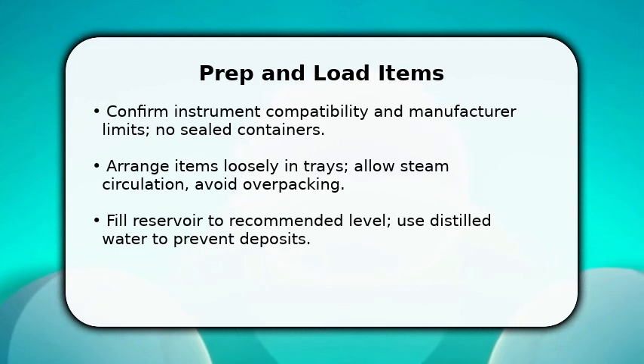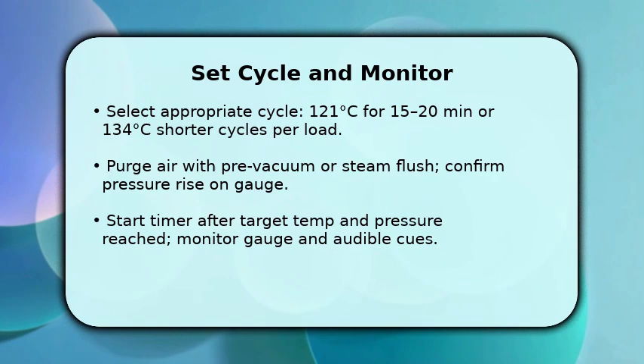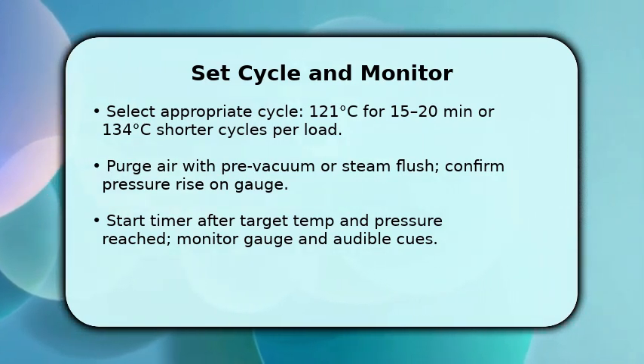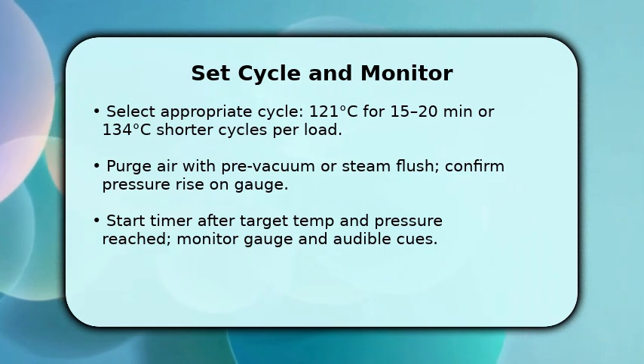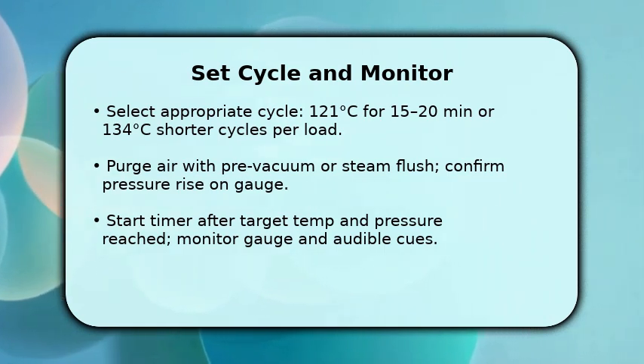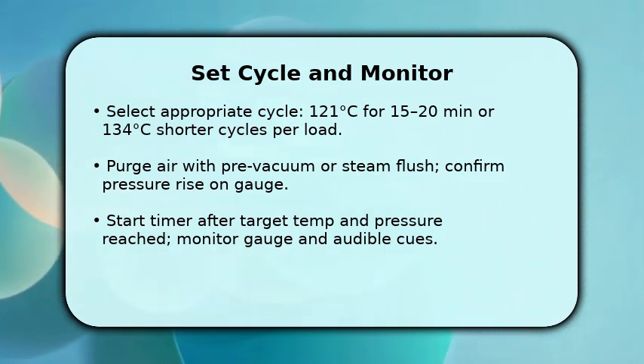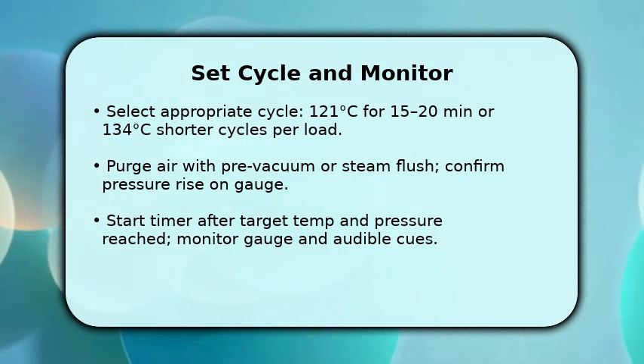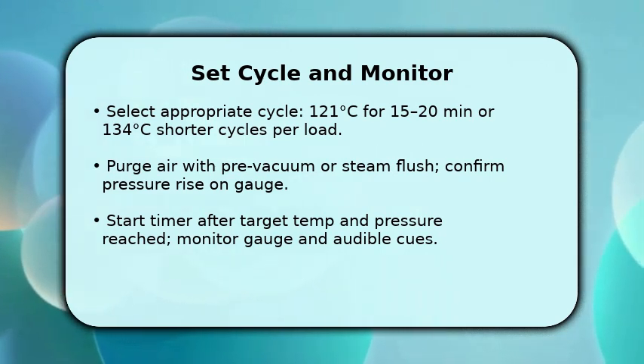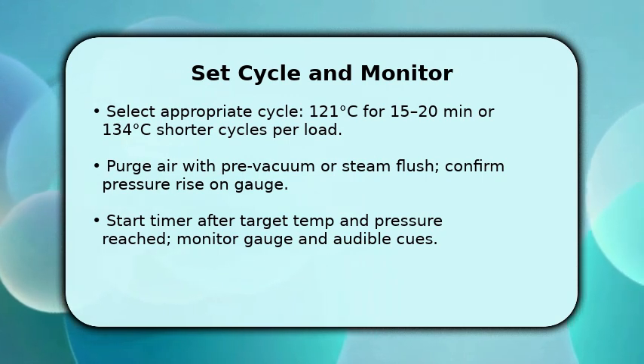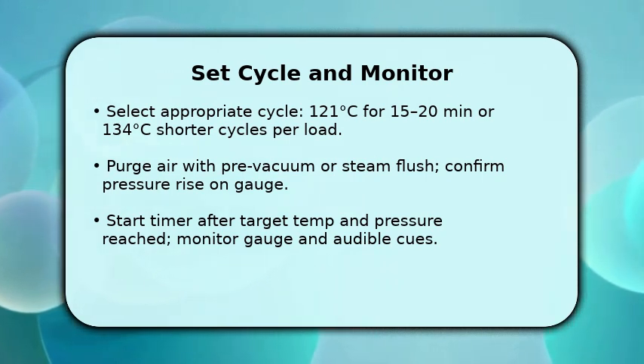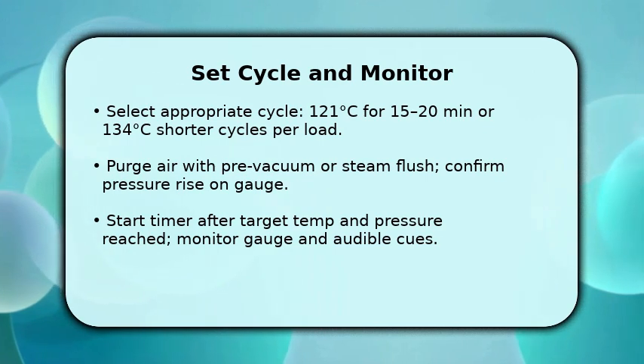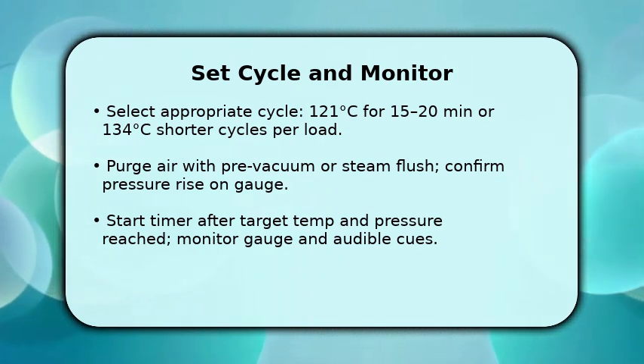You now select the correct cycle for the load. Choose 121 degrees C for 15 to 20 minutes for general items, or 134 degrees C for shorter cycles when allowed, because higher temps reduce time. Once started, ensure the machine purges air, either via pre-vacuum or steam flush, so steam contacts surfaces. Trapped air prevents sterilization. Monitor the pressure and temperature gauges, and start your timer only after the set point is reached. If readings fluctuate, slow the process.